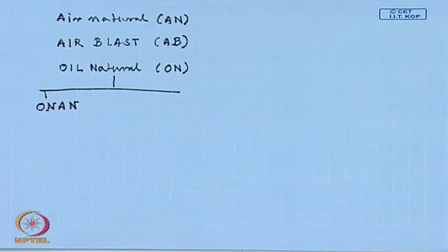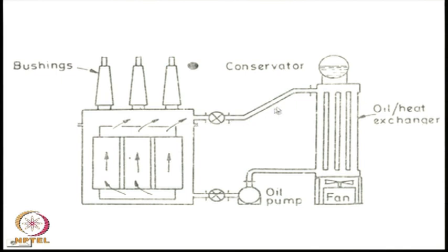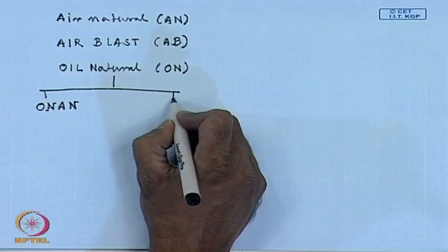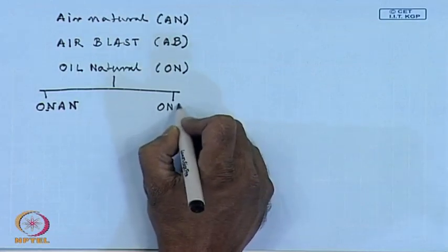However, for larger transformers, natural cooling by air is not sufficient, in which case it becomes necessary to blow air to cool the heated oil. For this, normally the hot transformer oil is carried to an external heat exchanger through a piping arrangement, and the heat exchanger is where the heat is transferred from the oil to the surrounding air, and it is usually cooled using a fan. This method is called oil natural air forced.